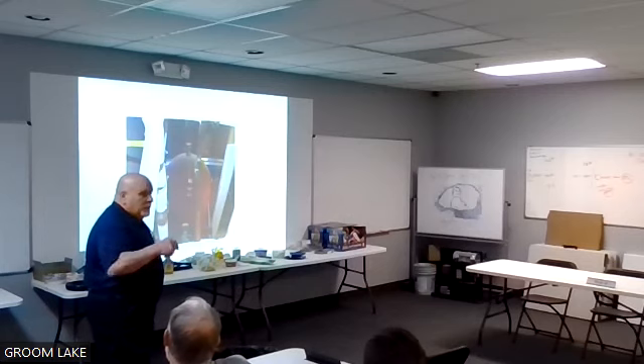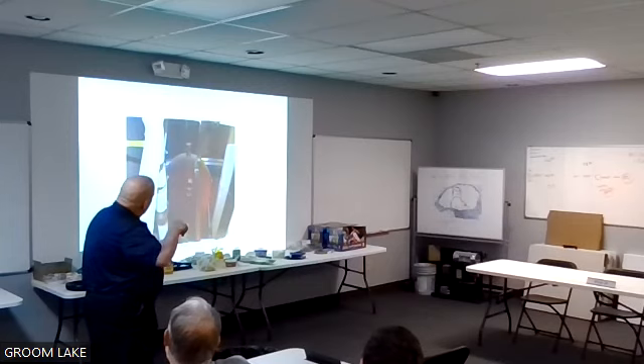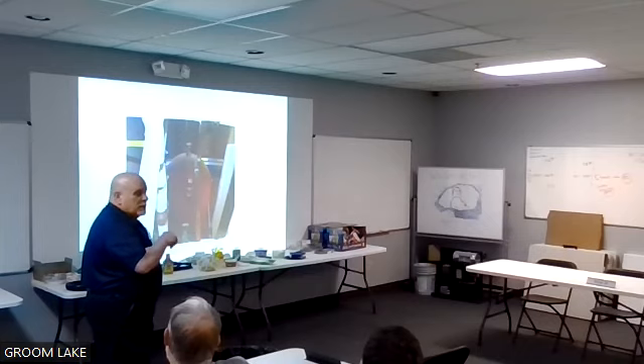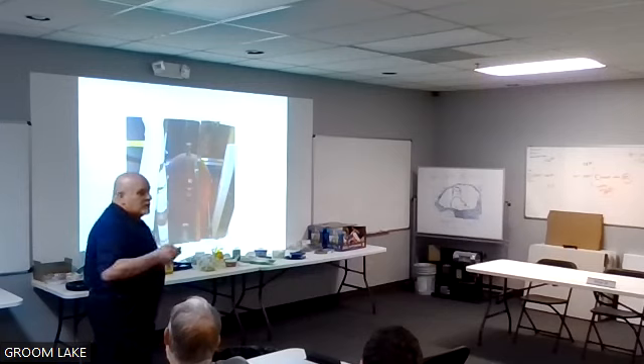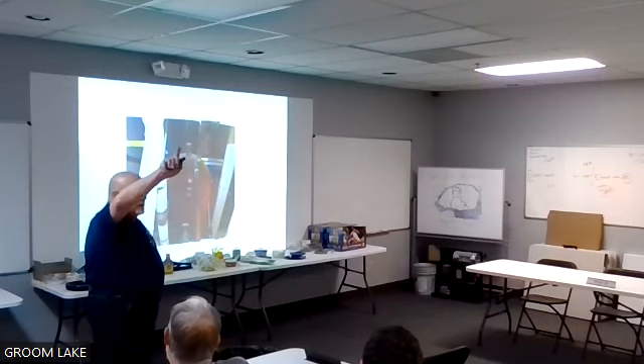Then as you heat up, this tank will go higher and higher and higher. As it cools down, it'll drop back out. As the expanded water fills, it's just going to fill itself up. As it cools down, it's going to push it back into the system. But if this is totally flooded, and I'm at cold iron, I have nowhere for that expanded water to go. So then you start lifting your relief valves, and your pressure just goes exponentially up through the roof.